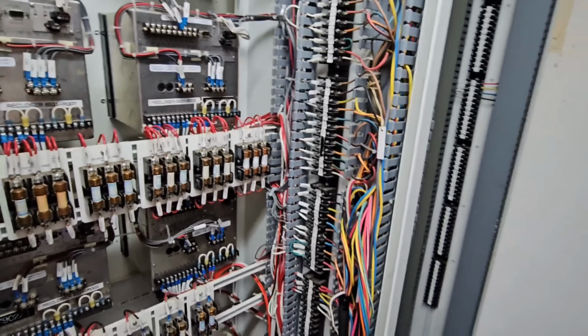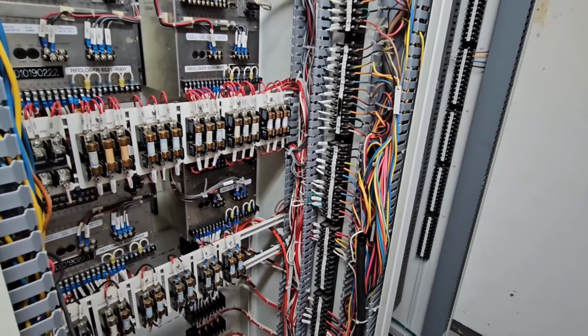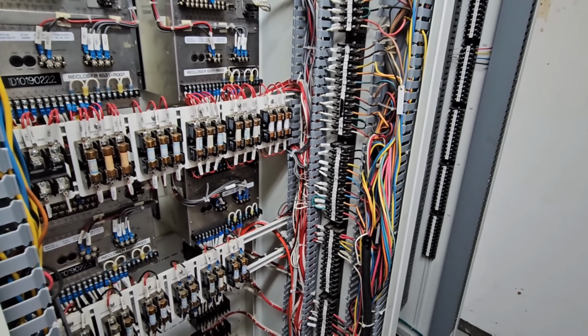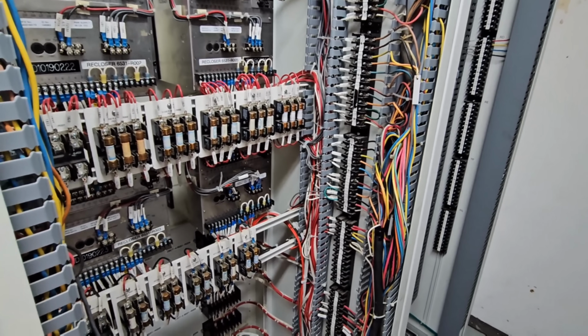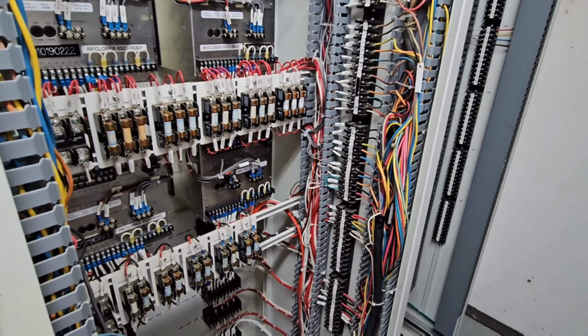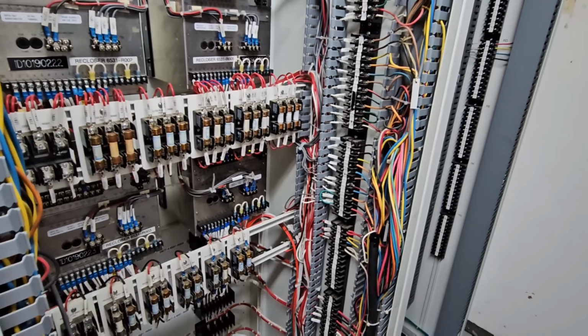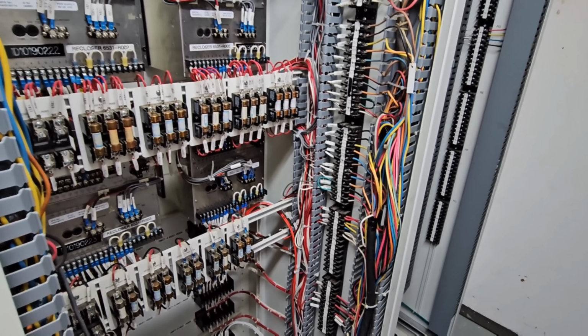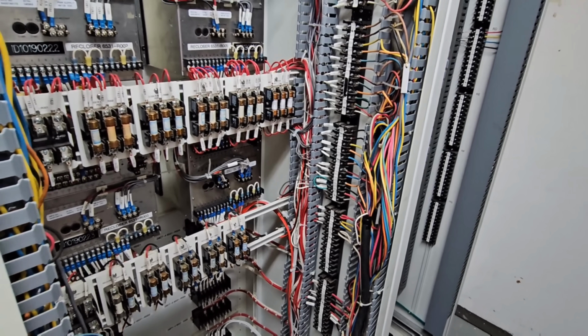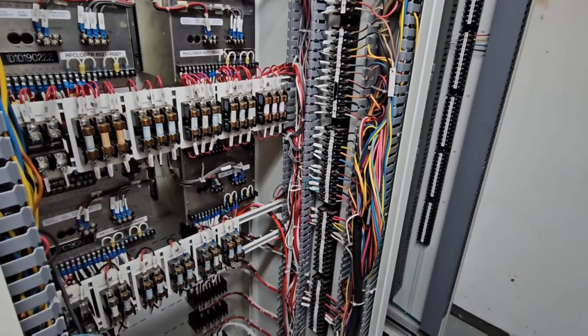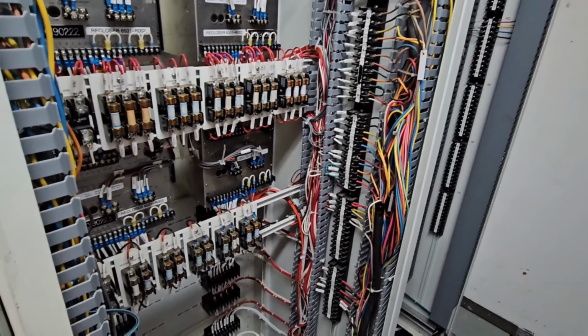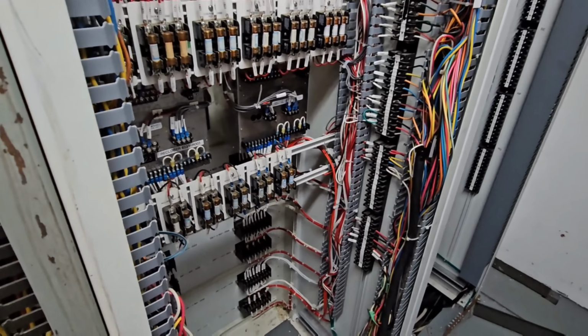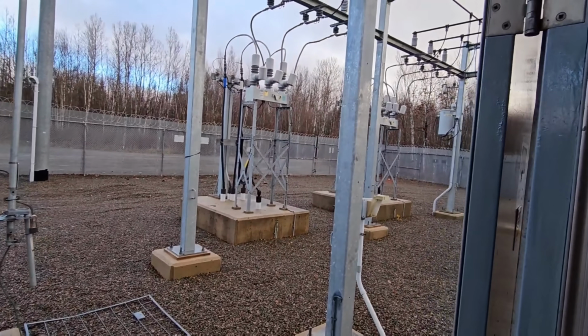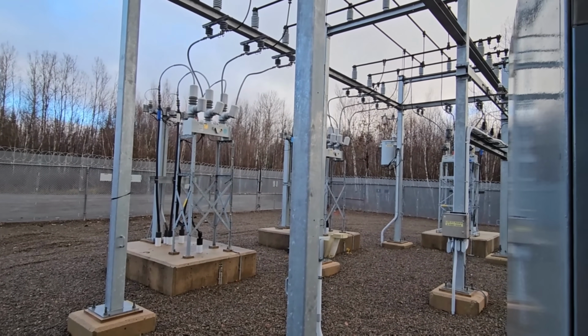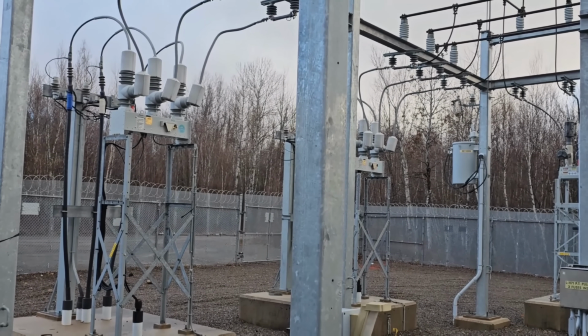So this is where me and my partner come to next, while the guys at the office, now that we found the problem, are loading up all the required material to make the repairs. Again, I could be out on the distribution system trying to pick up a few customers. However, we want to get the major problem, that job, on the go first. So we operate all those switches, which also isolates these units out in the field so that when the line comes back on, it's not going to overload the system.